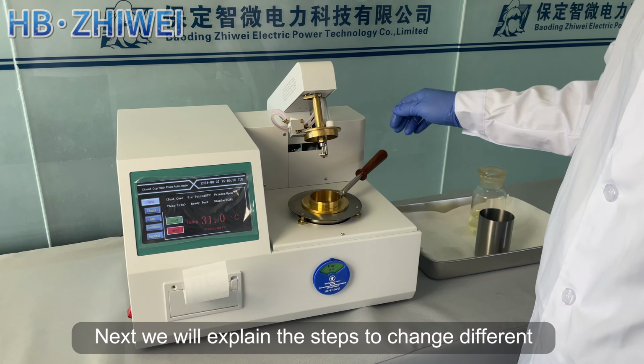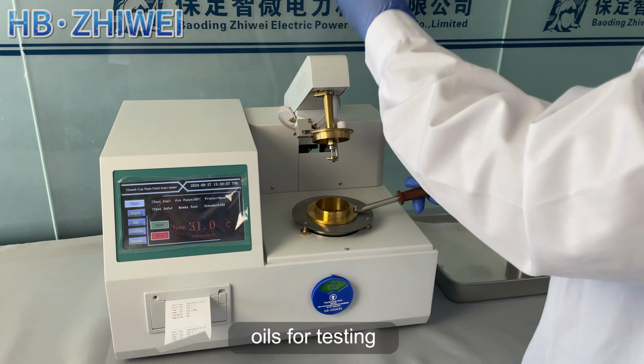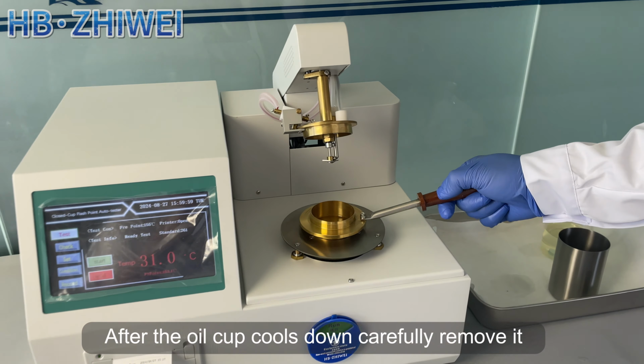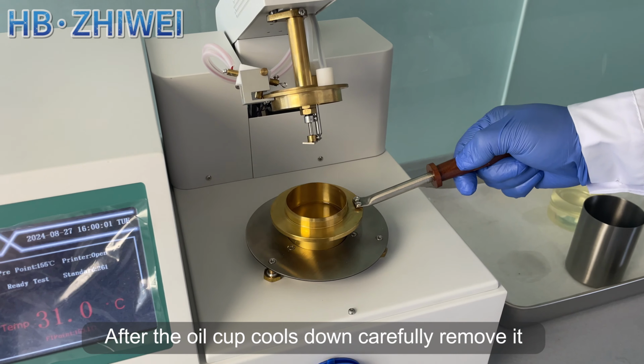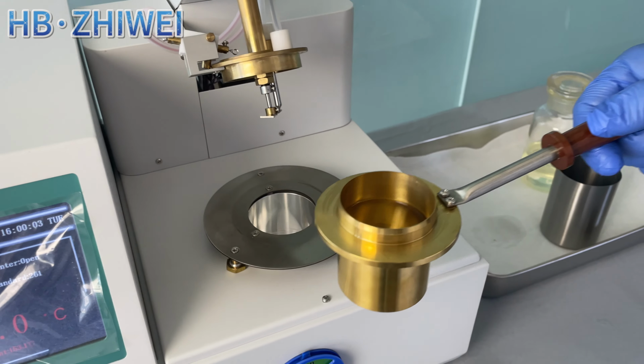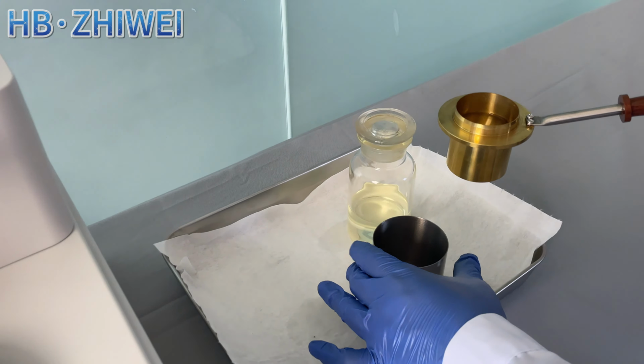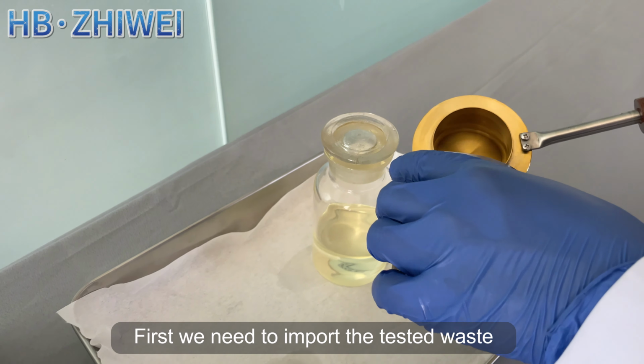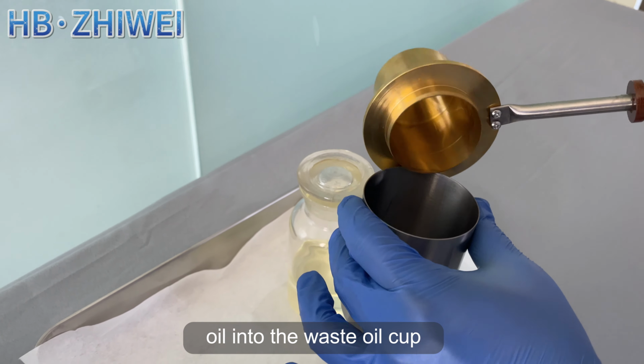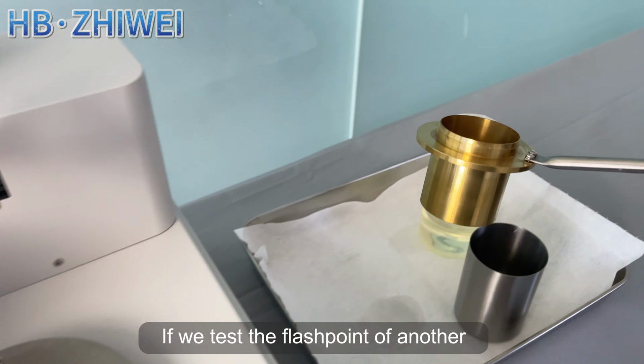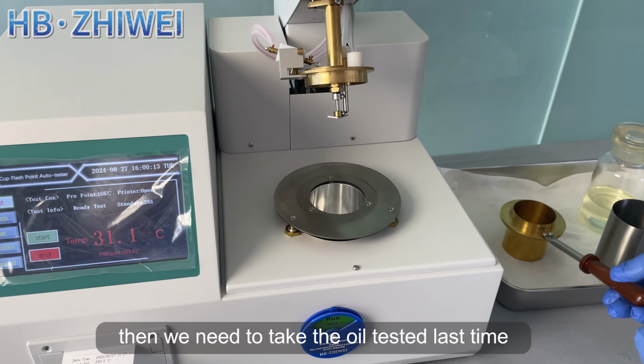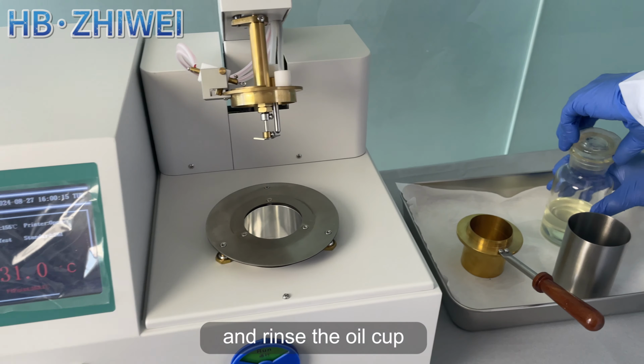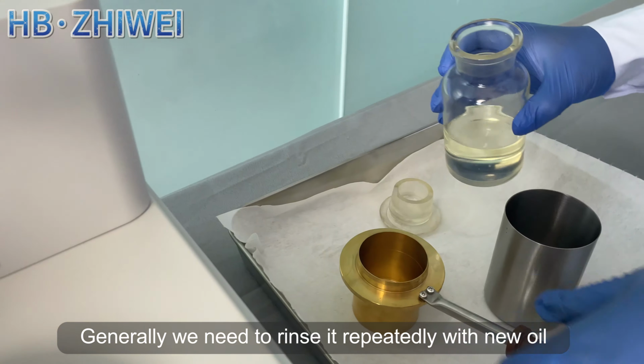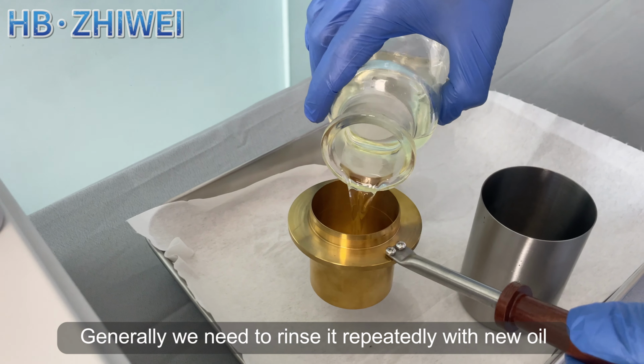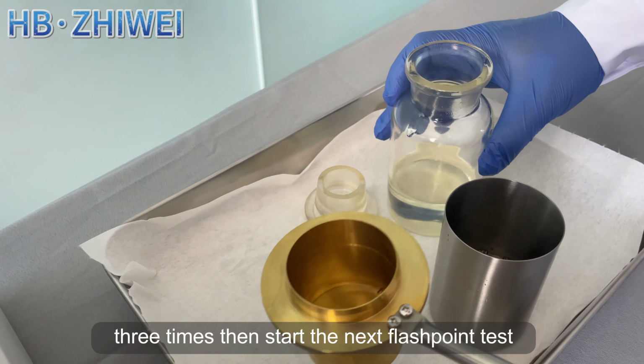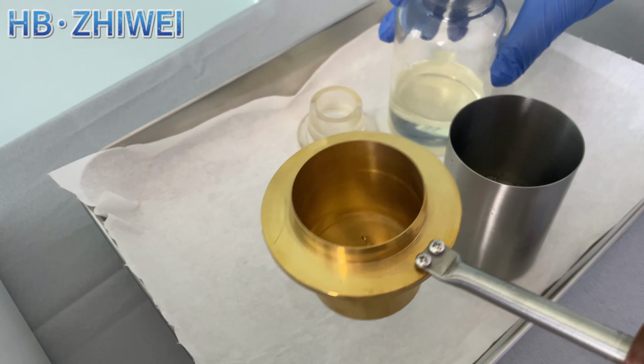Next, we will explain the steps to change different oils for testing. After the oil cup cools down, carefully remove it. First, we need to import the tested waste oil into the waste oil cup. If we test the flashpoint of another different type of oil, then we need to take the oil tested last time and rinse the oil cup. Generally, we need to rinse it repeatedly with new oil 3 times, then start the next flashpoint test.